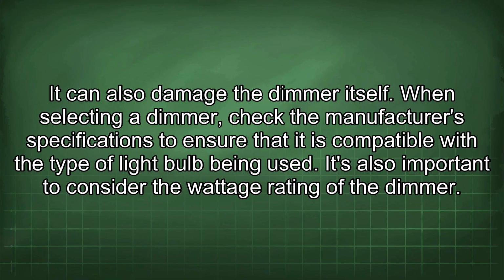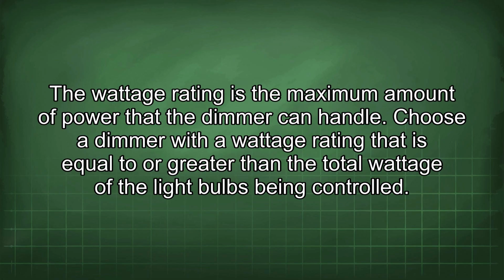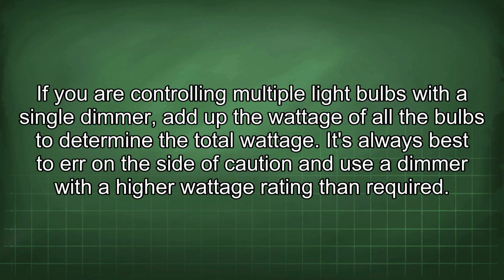When selecting a dimmer, check the manufacturer's specifications to ensure that it is compatible with the type of light bulb being used. It's also important to consider the wattage rating of the dimmer. The wattage rating is the maximum amount of power that the dimmer can handle. Choose a dimmer with a wattage rating that is equal to or greater than the total wattage of the light bulbs being controlled. If you are controlling multiple light bulbs with a single dimmer, add up the wattage of all the bulbs to determine the total wattage.